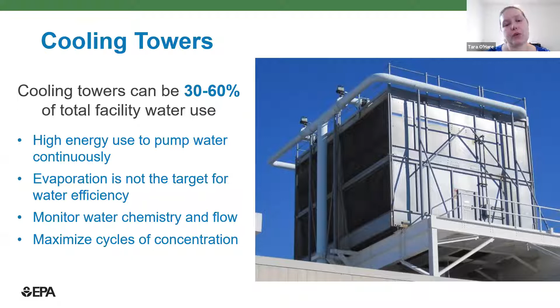The main goal here with cooling towers is to maximize the cycles of concentration, and that's really just an indicator of the number of times that water can be recirculated through the system before you discharge it to the sewer. And it's basically controlled and limited by the concentration of minerals in the water that can build up over time. So if you can work on this, increasing cycles from 3 to 6 cycles reduces makeup water by 20% and blow down by 50%. So it can be a huge savings. In order to monitor this, we encourage you to install submeters on both the makeup and blow down lines, so you can monitor flow and make sure that it's actually working as intended.